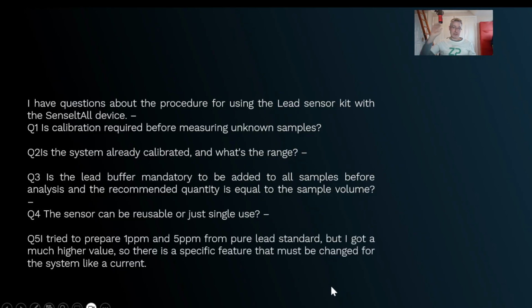For your sample, let me focus, that 5 ppm is very high, by the way, especially for lead. But 1 ppm is an easy piece of maths for me. If I take 1 ppm and do a 1 plus 9, that will bring it to 0.1 ppm, which is 100 ppb. Make sure that you tell the software that was a 1 in 10, and it should be able to deal with that at that point.